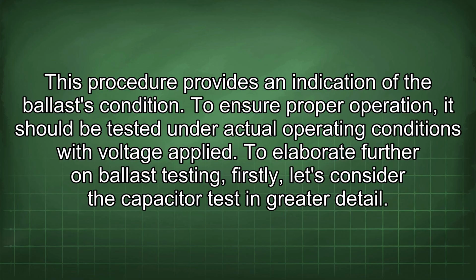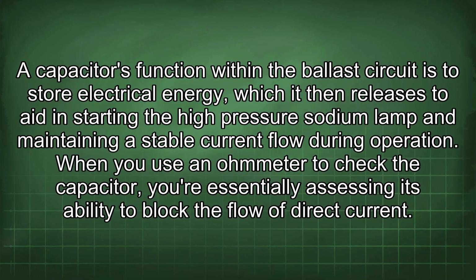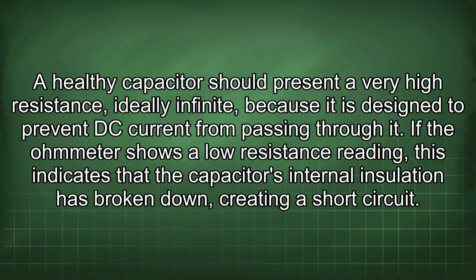To elaborate further on ballast testing, firstly, let's consider the capacitor test in greater detail. A capacitor's function within the ballast circuit is to store electrical energy, which it then releases to aid in starting the high-pressure sodium lamp and maintaining a stable current flow during operation. When you use an ohmmeter to check the capacitor, you are essentially assessing its ability to block the flow of direct current. A healthy capacitor should present a very high resistance, ideally infinite, because it is designed to prevent DC current from passing through it.